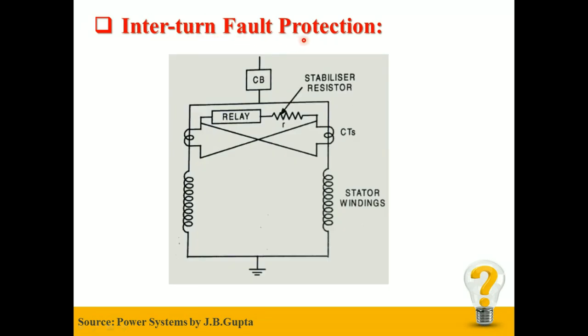Inter-turn Fault Protection: The protection scheme for inter-turn fault is shown in the figure. The primaries of the CTs are inserted in parallel paths, and the secondaries of the CTs are cross-connected as you can see in the figure. When there is no fault, the current flowing through the parallel paths of the stator winding will be equal, so no current will flow through the relay. But during an inter-turn fault in the phase winding, the currents flowing through the two parallel paths will be different, and a current proportional to the difference of the two currents will flow through the relay, which will send a trip signal to the circuit breaker in order to protect the stator winding against the inter-turn fault.